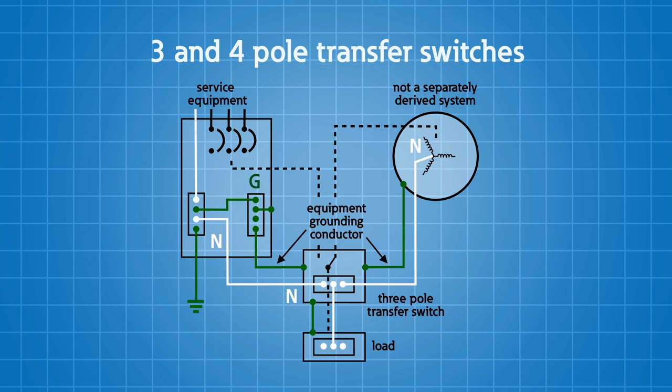So this is a basic layout of a transfer switch with a generator in a system. Now, sometimes people will drive a ground rod and bond the generator hull or the structure to that ground rod, and that ground rod is supplemental.